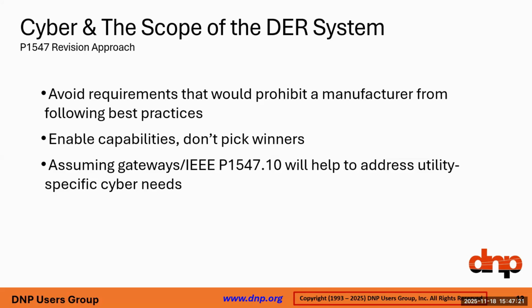We may specify capabilities like interfaces used to configure protocol parameters, such as the IP address or updating certificates, and specify that those must be behind some form of authentication, but leave the form of authentication up to industry to decide. We're also looking at setting defaults for protocols while leaving room for area EPS operators and DER owners to apply alternate methods as needed. Finally, we're looking at how gateways and related standards like 1547.10, which defines DER gateways, can play a role in addressing utility-specific cybersecurity needs.